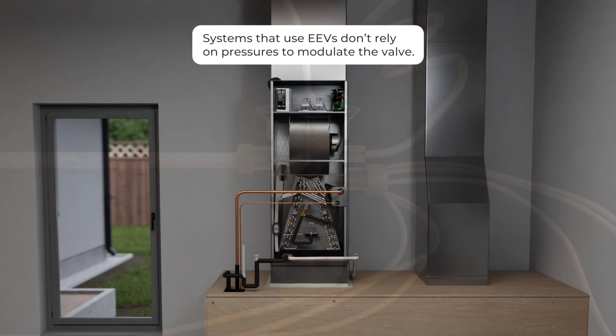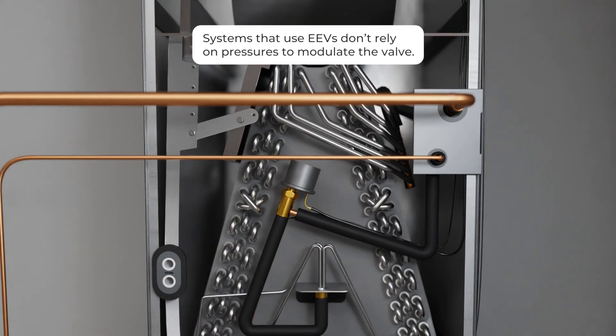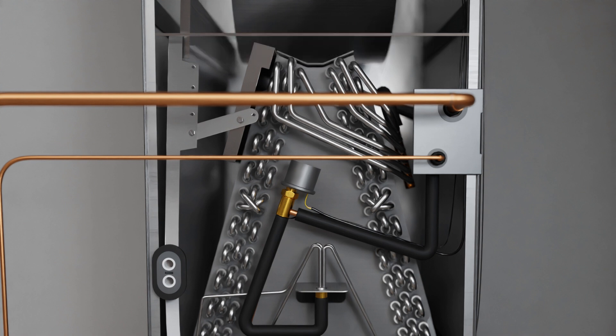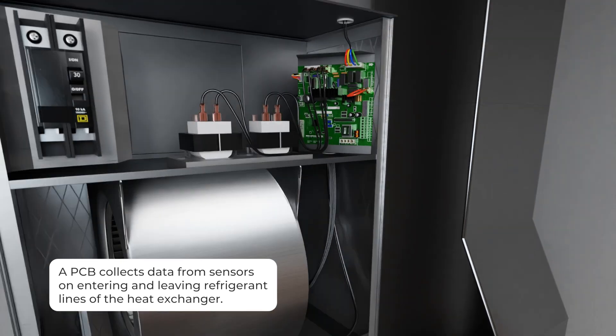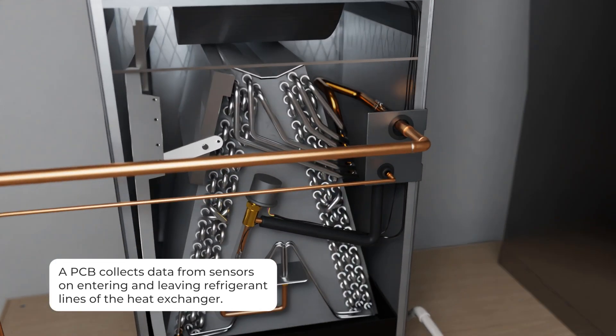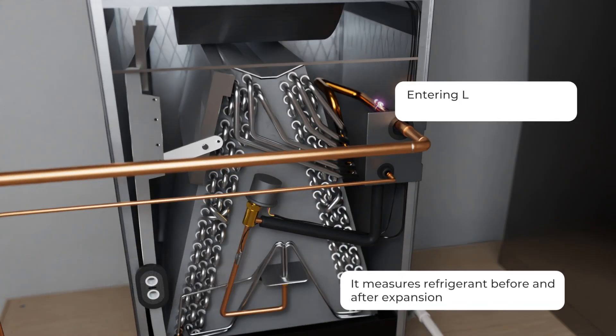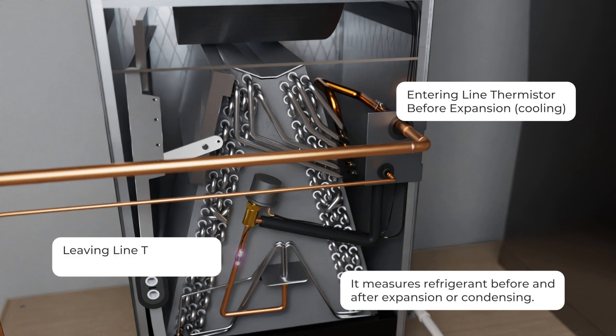Systems that use EEVs don't rely on pressures to modulate the valve. Instead, a printed circuit board, or PCB, collects data from sensors on both entering and leaving refrigerant lines of the heat exchanger, essentially measuring refrigerant before and after expansion, or condensing depending upon the mode.